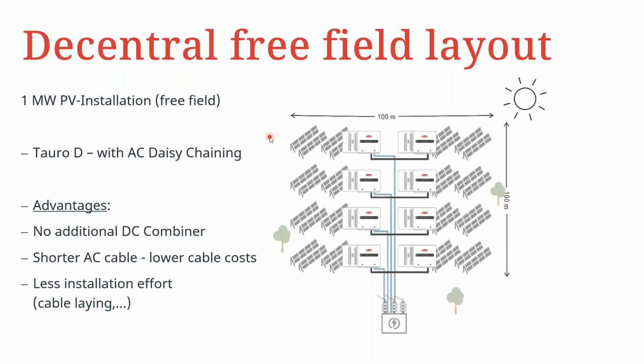This particular topology comes with various advantages. First off, you don't have to use any DC combiner boxes because the inverters are right where the modules are, so you can connect them directly. The AC cables you run will be shorter, lowering AC cable costs, and you have less installation effort, especially when it comes to cable laying. We were supposed to run, say, 8 cables for the AC side, but we're just laying 4, which saves a lot of effort and cost.